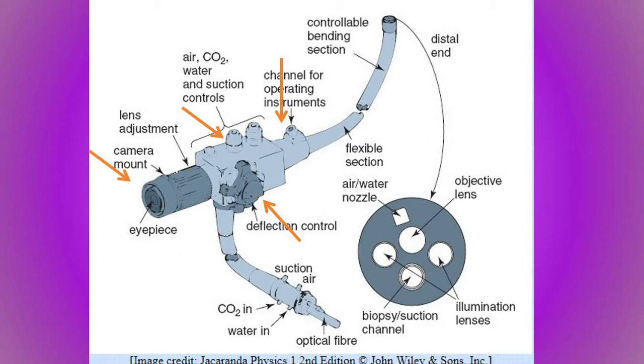This channel, along with leads of fibre optic cables, the air and water channels, the control cables, and the objective lens, all finish at the distal end of the controllable bending section of the endoscope. All of this makes up the shaft, which is usually only about 10 mm in diameter and can sometimes be up to 2 meters long. It is flexible and coated in steel and plastic to make it waterproof, easy to maneuver, and prevent against chemical damage. On the bottom of the main body is a channel to pump CO2 and water in and run the fibre optics through to connect a TV monitor or a recording device.